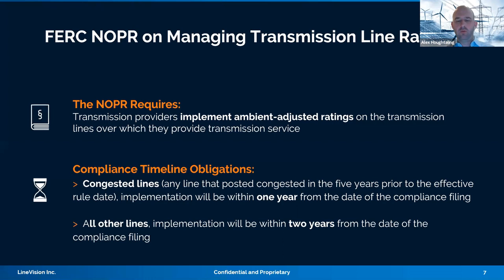So what does the FERC NOPR require? First, it's looking at ambient adjusted ratings as a mandate, saying for any line that has posted congestion in the past 5 years as of the date of entry into the Federal Registry, you will need to do at a minimum ambient adjusted ratings on those lines. That would include anything at or above that classification, so dynamic line ratings would count, and of course ambient adjusted ratings count as well.